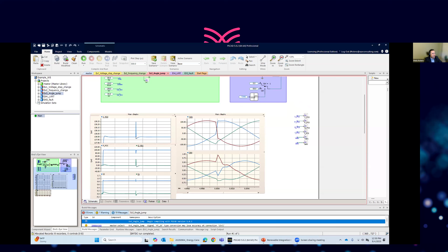Now I have a bit more complicated test. I wanted to test the LVRT, low voltage ride-through capability of the IBR. I changed the voltage magnitude with this profile, and then wanted to see what's happening to the power. As we expected, when the voltage goes to zero, the active power and reactive power go to zero. But in ID and IQ we can see better, because active and reactive power are I times V. So when V is zero, active power is zero as well. But what we expected is that when the voltage goes to zero, IQ should go to the maximum amount to try to inject more reactive power to support the grid.